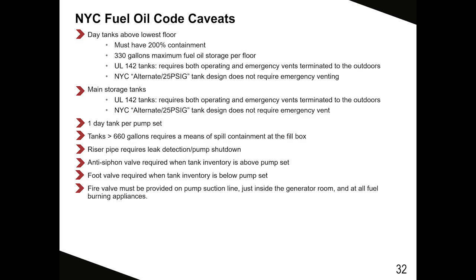UL-142 tanks require both the operating and emergency vent lines terminated outdoors. New York City alternate tank design, 25 PSIG rated tank, requires its operating vent be terminated outdoors. Also, the New York City alternate tank design tank does not require an emergency vent. One day tank per pump set.